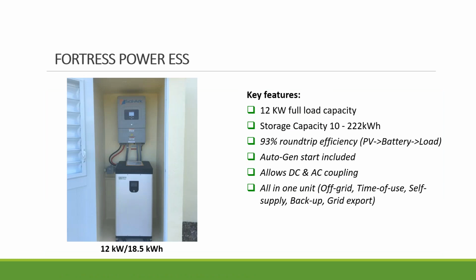So I'm going to talk about two types of hybrid inverters on the market now. The new ones have the charge controller and the inverter all in one unit, and this is a cookie cutter solution that we offer with a 12 kW inverter and eVolt 18.5. You can, of course, expand the systems. In terms of storage capacity, you can go from 10 to 20 or more. It's very efficient, 93% round trip efficiency. That's also very important when you look into the energy storage solution.